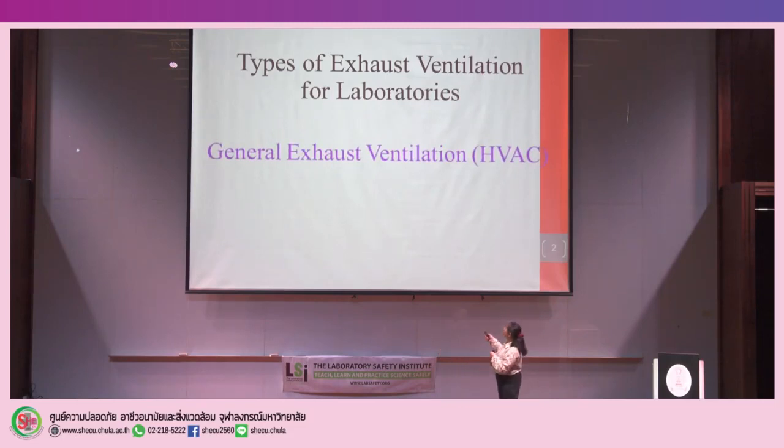General ventilation means the room ventilation, which now you don't have. Keep in your mind, you don't have it. You have to have a big fresh air unit that brings in air from outside at 40 degrees, changes it to 25, and brings it into our room, and normally we have to get it all out together. So it's very, very expensive. I can understand that academic institutes cannot do that. But I would like you to at least consider having part of it as fresh air. I mean 5%, 10% for your breathing.